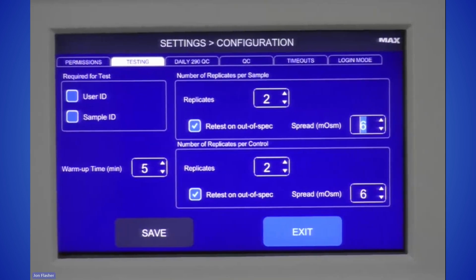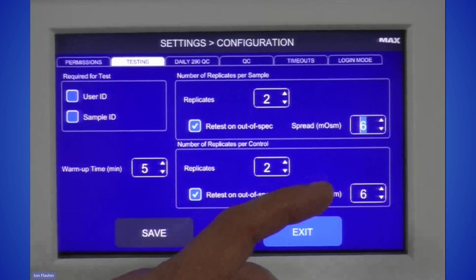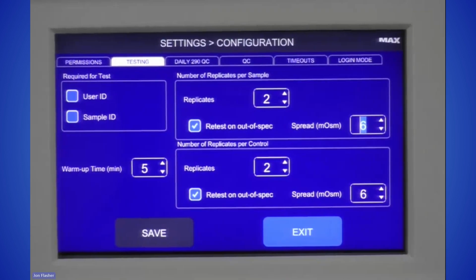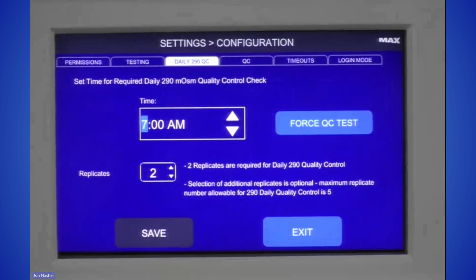If it's outside of a certain range, right now it's set to a 6 milliosmol spread, then you can also pre-program it, checking that little box on the bottom left-hand of the number of replicates per sample area. You can also pre-program it to automatically retest to see if the next test is within the acceptable spread before moving forward with the rest of the tests. And you can do the same thing on the bottom right for the QC as well. So it's a really handy feature for not having to manually go back and do everything outside of just loading the instrument on the turntable and hitting play, just letting it do its thing. Okay.